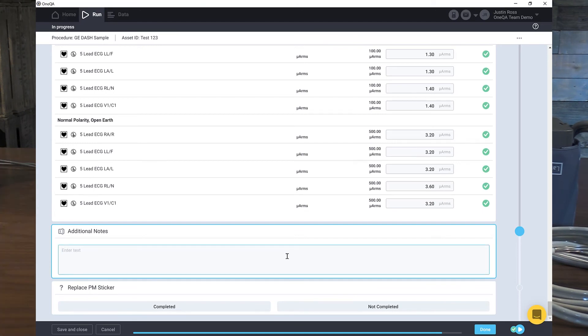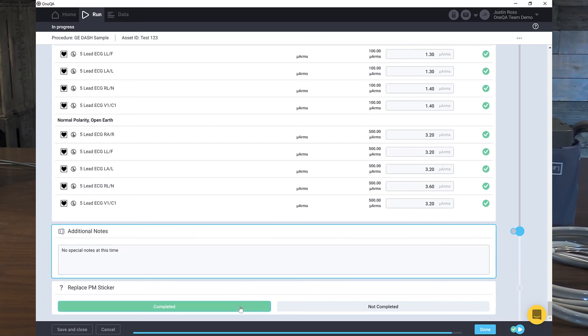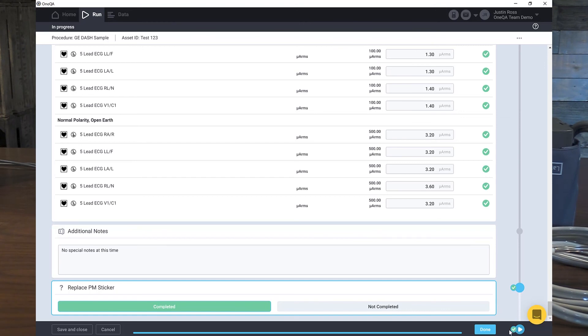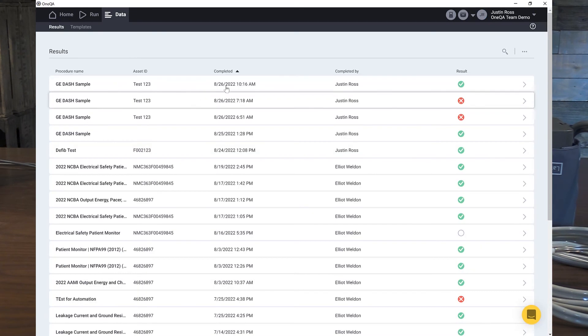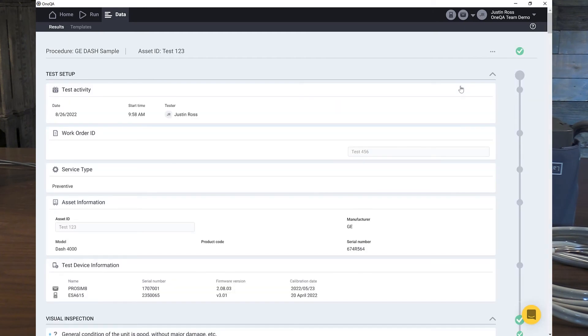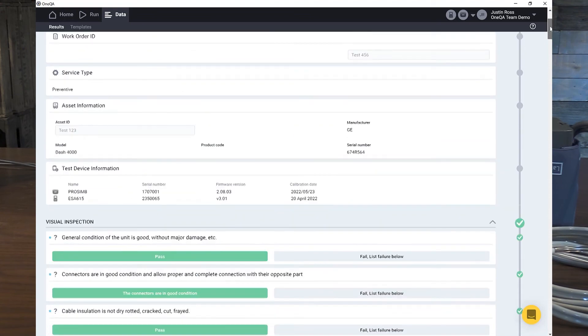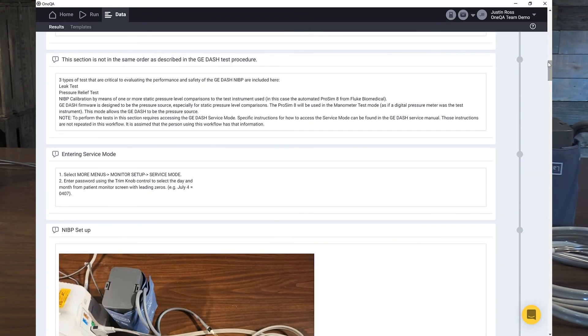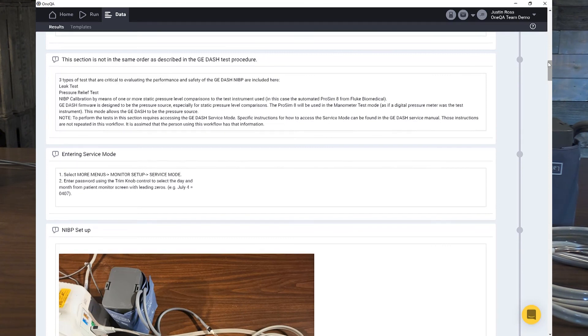And we'll put a PM sticker on it. That's our last green checkbox over here. At the bottom, we have a green light, which means the PM procedure has been completed. We'll click done. And this is going to go ahead and save it over to our reports. From here, this is our results. We can make different forms of a report. We can do a modified report. We can do the all report, all the data. Here's our test. We just passed it. So we can modify these reports and what data you want to come over to your PC. So you'll see in this example, it has all the data included into this. But we can also get rid of a lot of these fields that you don't want brought over, like the pictures and stuff. And simply import this back into your CMMS platform or attach it as a PDF. Thank you very much for joining us, and we'll see you in our next video.